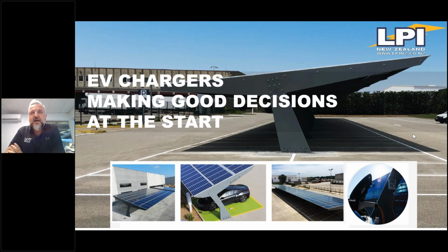We are definitely monitoring through the CTs that we install, monitoring the power consumption coming into the building against the contractual power or demand of the building. Our device, either through the maximum demand operation unit or through dynamic load management, will ensure none of your protection devices trip on overload - it will ensure you don't trip the supply to your chargers. I'm not sure if I'm answering the question correctly, because he was mentioning something to do with the budget between the two buildings.